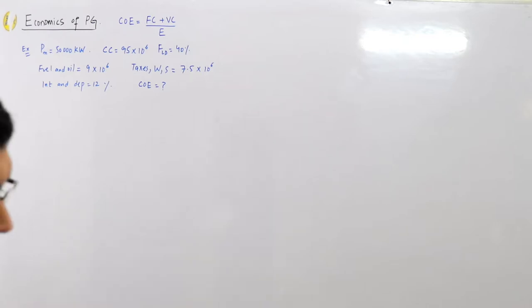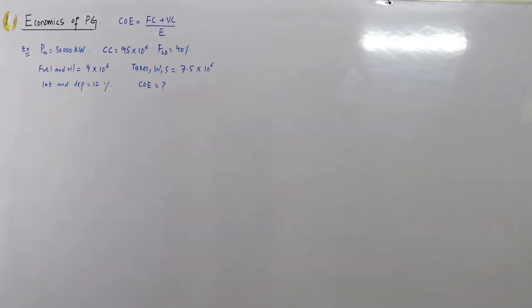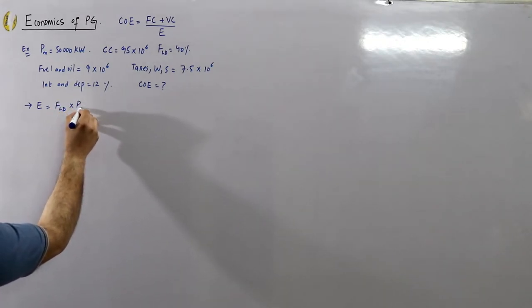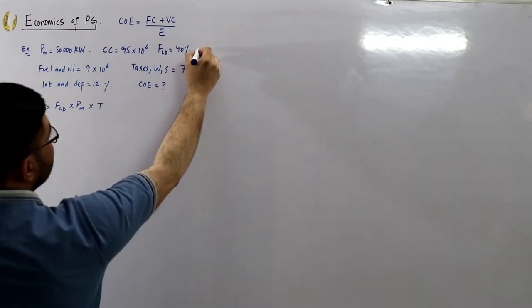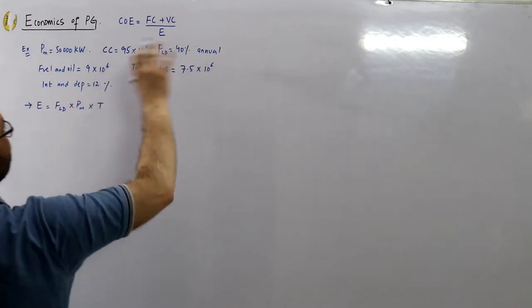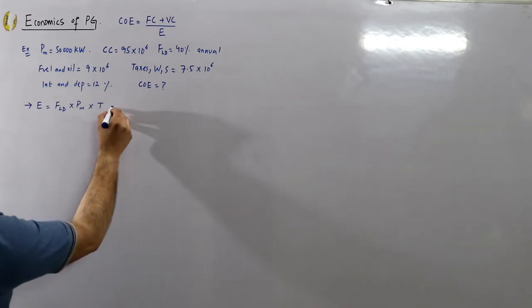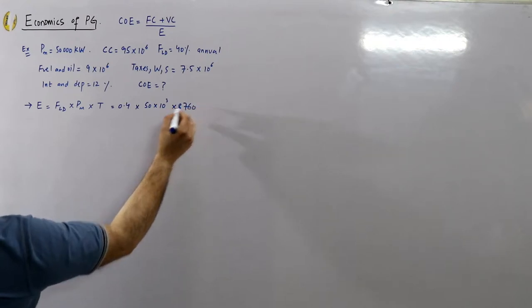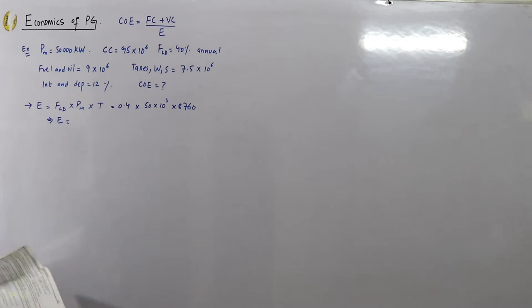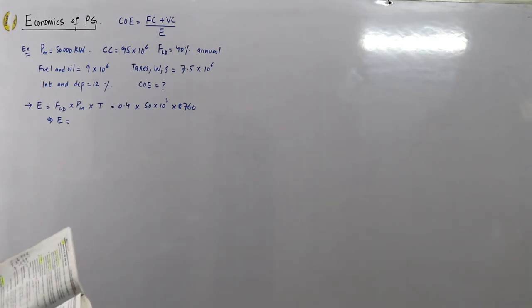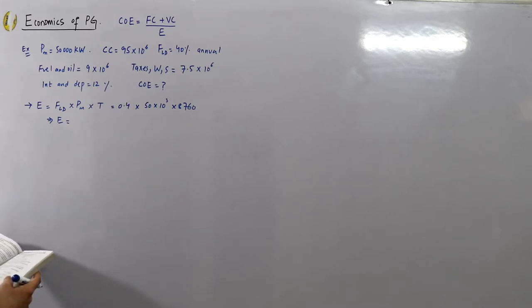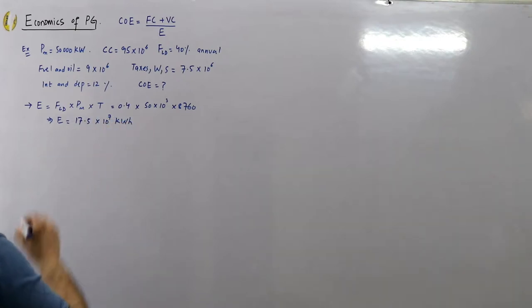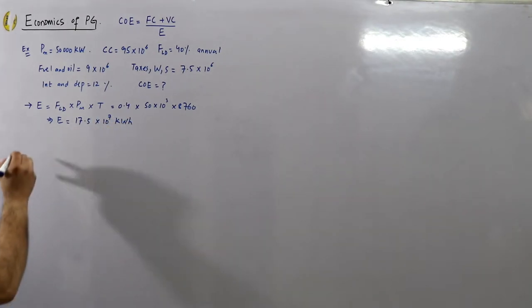First, find the energy units using the load factor formula: energy units = load factor × maximum demand × time. Since we have the annual load factor, calculations are done annually. So: 0.4 × 50,000 kilowatts × 8,760 hours = 17.52 × 10⁷ kilowatt hours.